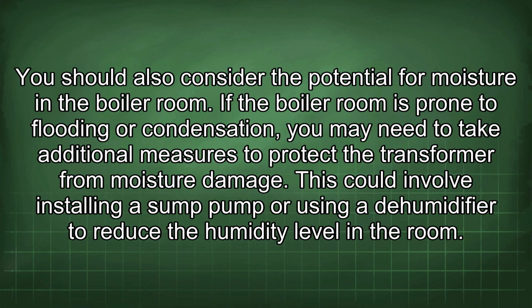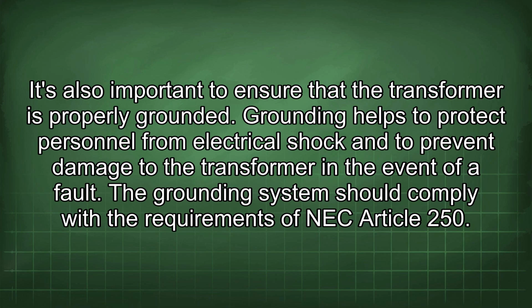You should also consider the potential for moisture in the boiler room. If the boiler room is prone to flooding or condensation, you may need to take additional measures to protect the transformer from moisture damage. This could involve installing a sump pump or using a dehumidifier to reduce the humidity level in the room. It's also important to ensure that the transformer is properly grounded. Grounding helps to protect personnel from electrical shock and to prevent damage to the transformer in the event of a fault. The grounding system should comply with the requirements of NEC Article 250.